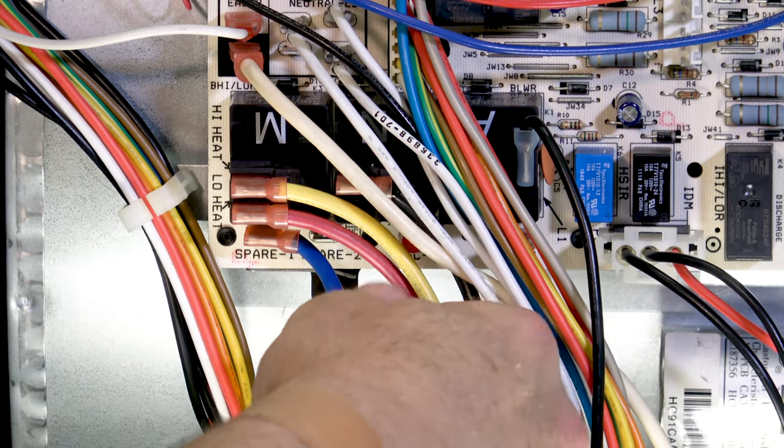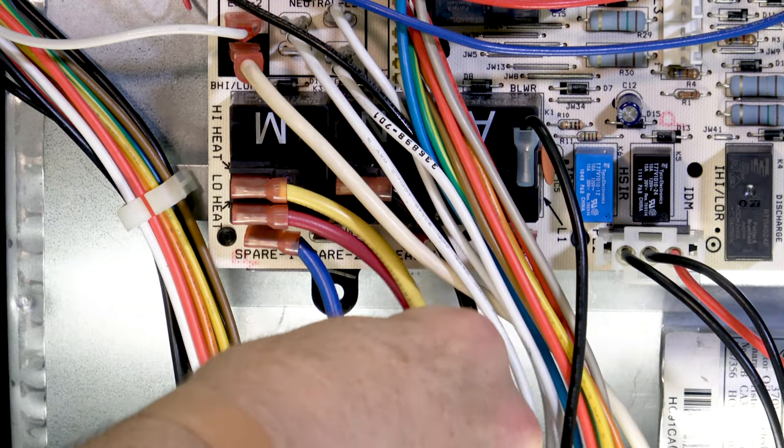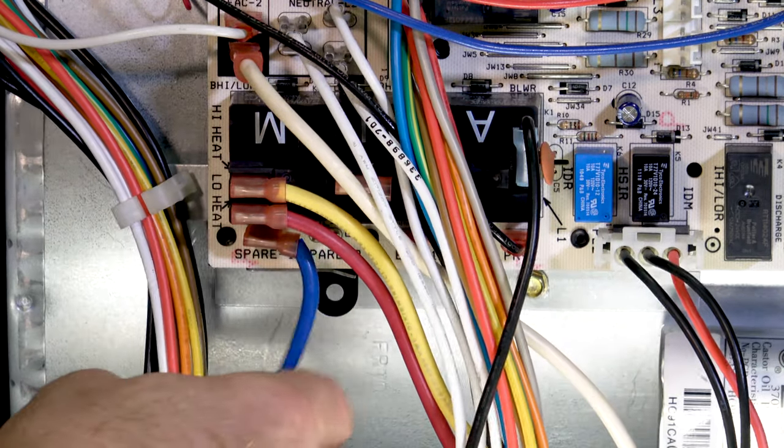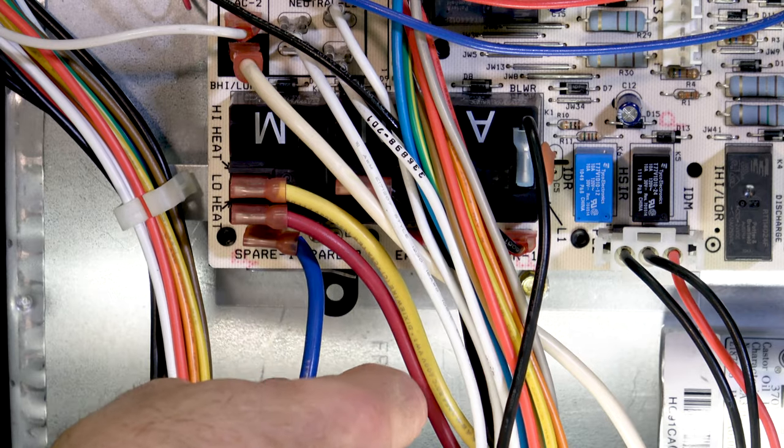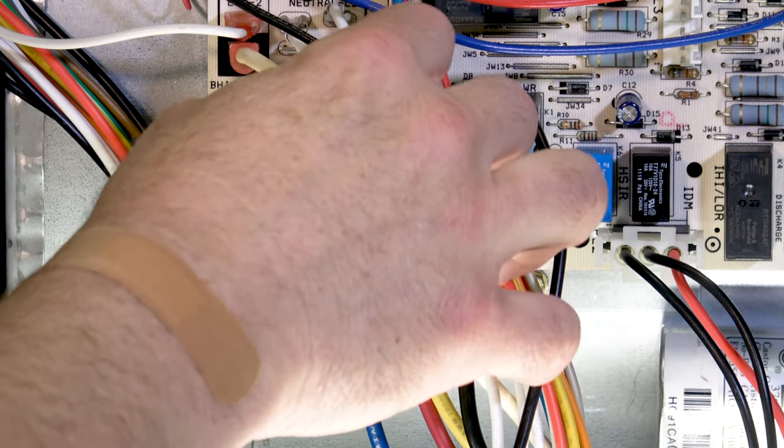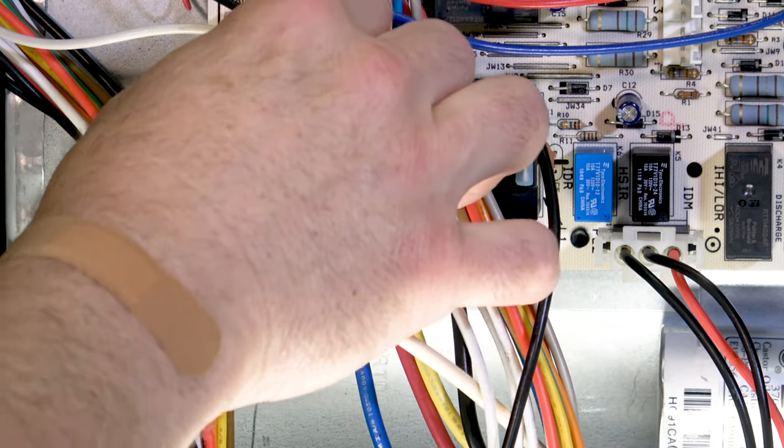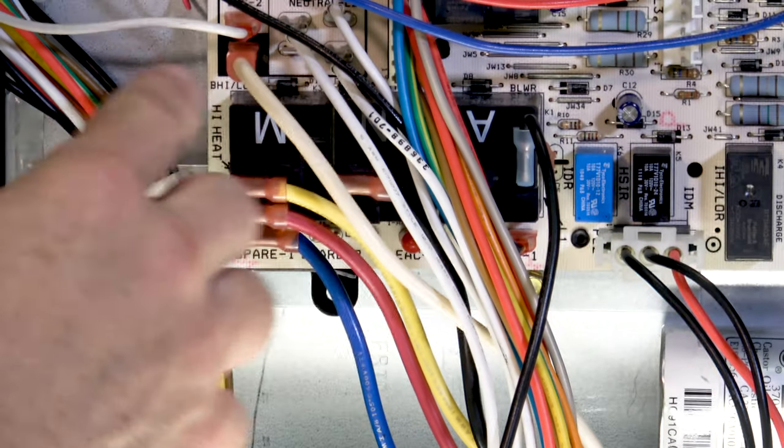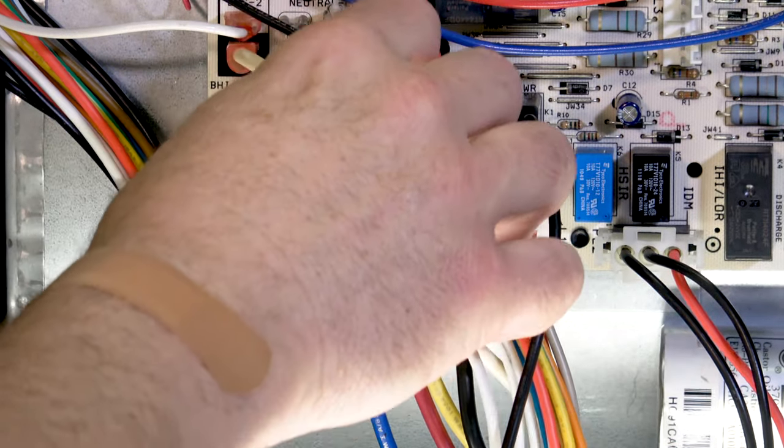The blue which is the medium low is on our spare terminal on the bottom of the board so that is not being used at all, and then the white wire is on our neutral terminal which is right above all those, which is also tagged blower on the neutral plugs on the board.